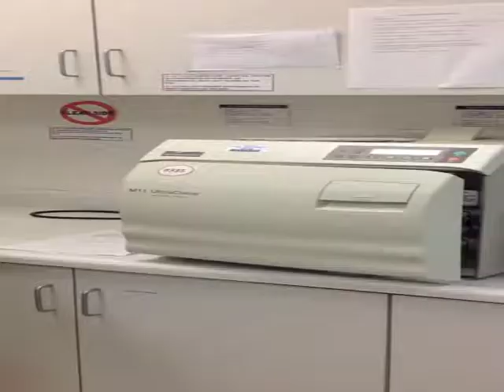This is when you need to spore test the mid-mark. You are going to, in a similar fashion, remove the strip from the envelope and place the spore strip in the very back of the autoclave while it's also loaded with instruments. You're going to load the autoclave, shut the door, and then run this on pouches just as normal. When the autoclave is complete, you will remove all the instruments and put them away in their correct place. Take out the spore strip, place it in the envelope, close the envelope, and use the instructions to fill out the front side of the envelope prior to handing it to Mrs. Shorey. Please make sure that you include your name.